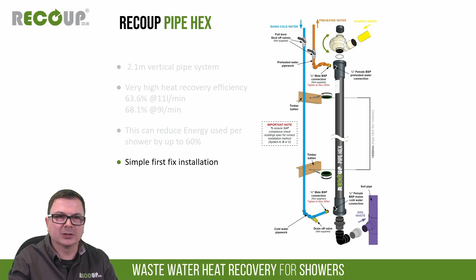A point to mention with the Pipe Hex, but also with all our products, is that all Recoup products have double-walled heat exchangers. You may ask, what does that matter? It allows us to be compliant with EN 1717. But the key point for developers or contractors is that it allows the trap for the outlet to be placed where it should be before our unit. So you trap before our unit, that grey water then goes through our unit and off to the waste, the soil pipe - meaning you don't need access past our unit at all.